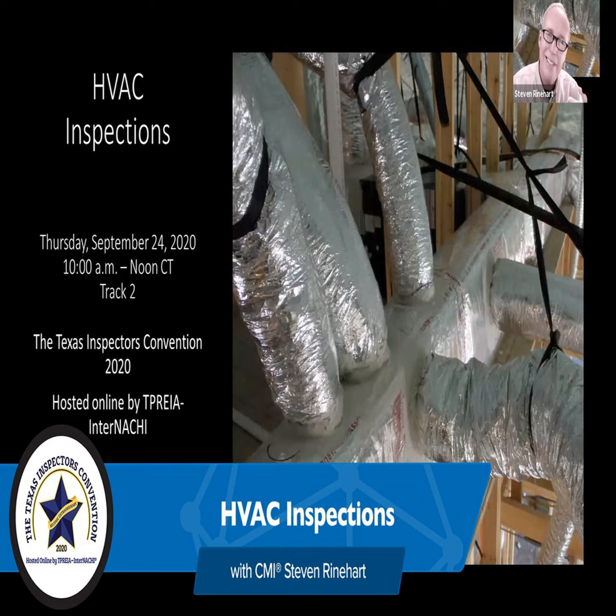Now we've got oxygen, moisture, and organic material, the three components of biological growth. That's it. The answer is condensation is the issue, typically from air leakage coming out. Just like aluminum windows conduct temperatures, ductwork typically moves air so fast it may not conduct, but it'll leak air. And that's where you get condensation and growing stuff.